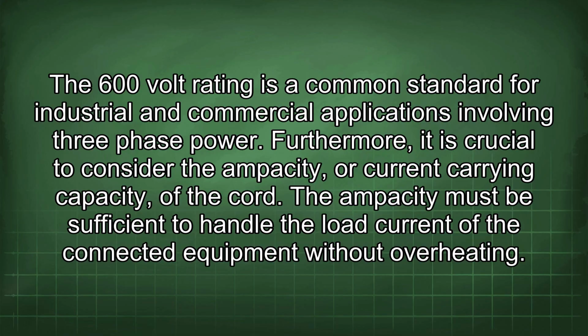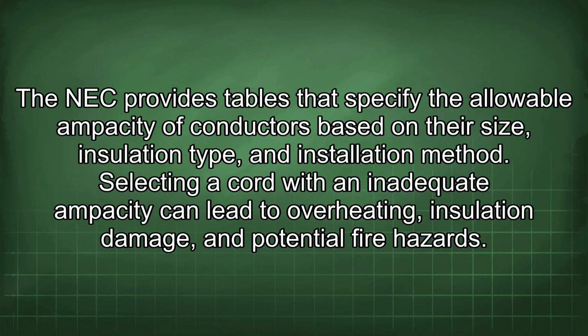Furthermore, it is crucial to consider the ampacity, or current carrying capacity, of the cord. The ampacity must be sufficient to handle the load current of the connected equipment without overheating. The NEC provides tables that specify the allowable ampacity of conductors based on their size, insulation type, and installation method. Selecting a cord with an inadequate ampacity can lead to overheating, insulation damage, and potential fire hazards.